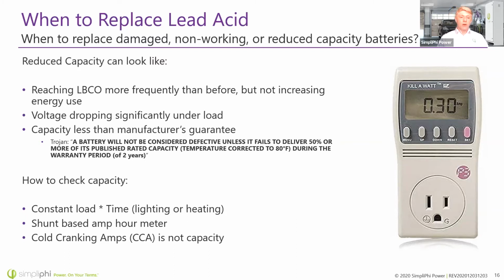I know a lot of lead acid battery installers have a little tester you connect to the lead acid battery terminals that tests the battery in about 5 seconds. That's not going to work here to check capacity, because cold cranking amps is not the same as capacity. And don't use your lead acid battery testers on lithium batteries either, because lithium batteries aren't designed to start engines necessarily. In some cases they are, but in general, cold cranking amps just isn't a useful metric for lithium batteries.